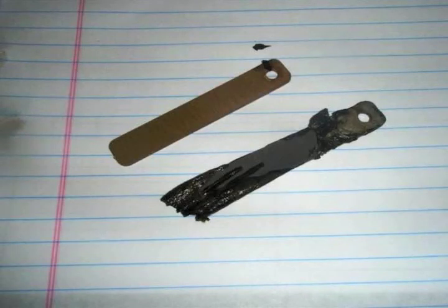Okay, so what's the impact of biological activity? These are corrosion coupons. If you've ever seen coupons, they're pre-weighed metal strips, either copper, and this one happens to be copper up here. This happens to be steel here. This actually was pulled out of a cooling tower system in the south. The black streaks you see right here is not general corrosion of a coupon. This is all biological growth growing on the coupon itself, which simulates what could be growing on your pipe surfaces, your tube sheets, or everything else. And underneath this stuff is what's causing the corrosion, and that's called biologically influenced corrosion.